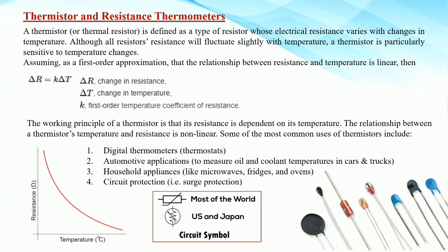With vastly improved formulas and techniques over the last 20 years, NTC thermistors can now achieve accuracy over a wide temperature range, like plus or minus 0.1 degree centigrade to plus or minus 0.2 degree centigrade, from 0 to 70 degrees centigrade, with excellent long-term stability. Typical NTC thermistors have a range of minus 55 degrees centigrade to 150 degrees centigrade, though some glass body thermistors have a maximum operating temperature of plus 300 degrees centigrade.